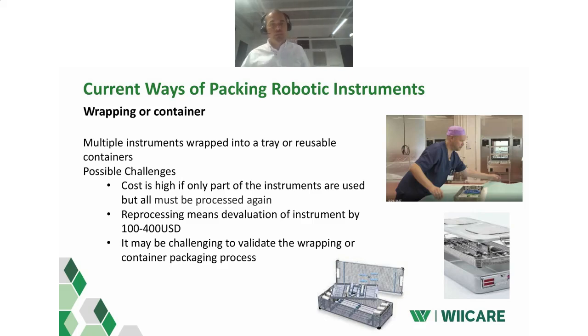One very common way that we see is to put multiple instruments into a tray and then wrap it, or put multiple instruments into a tray, put it into a container and close the container lid. This will probably be needed also in the future. But a possible challenge is that if you are putting more instruments into the tray than you are using in the actual operation, then you end up sterilizing or reprocessing instruments which have not actually been used in the operation. Because of course, after opening the container or the wrapped tray, you need to reprocess everything. And every time you reprocess them, there will be a devaluation of the instrument. So basically, it's a waste of the instruments because you can only sterilize them or reprocess them a certain number of times.